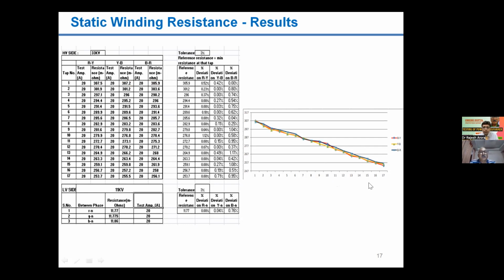Then the test is also done on the LV side. On the LV side it is done basically to know if there are some issues with the connections, etc. Otherwise, LV side resistance is very small, so not much importance is given. But if the deviations are beyond acceptable limits, then there may be some issues. Sometimes we have seen cases where a hot spot or high resistance has developed between the LV bushing and the winding connections. That kind of issue may be traced through this test if we perform it on the LV side also. Next.